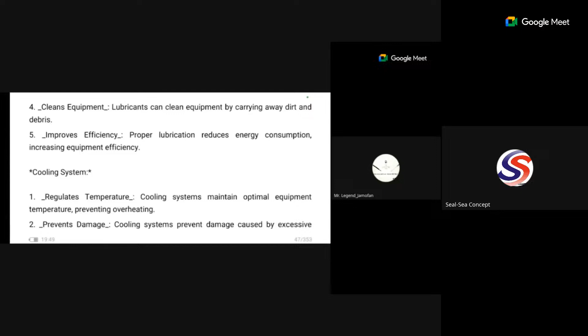When you look at your electric motor, you can have overheating, or an insulation failure if the cooling fan fails. When there's overheating in a machine, if any part is insulated, the insulation will break down. All those wires used to coat your coil inside your stator, your armature, will actually burn. Once one phase is already touching the other phase, there will be a problem, a short circuit in the machine, and the machine will have to shut down. So the cooling system regulates the temperature, and by doing so, it prevents damage, because high or excessive temperature will damage parts of the machine.